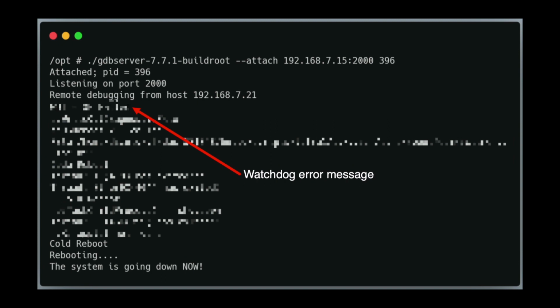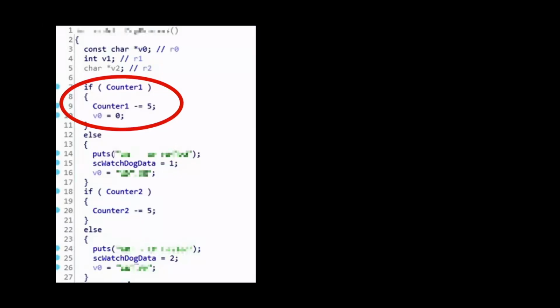Because the error messages were left in and because symbols were left in, it was actually very easy to track down this line of code. As you can see here, there are about three counters being decremented by 5. When the counters hit 0, it triggers the watchdog timer, which trips and the device reboots.